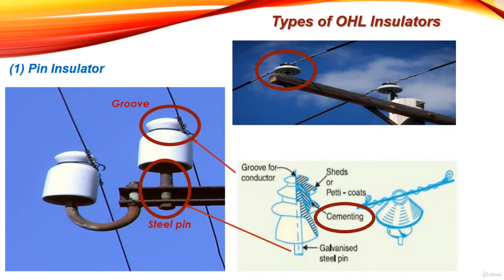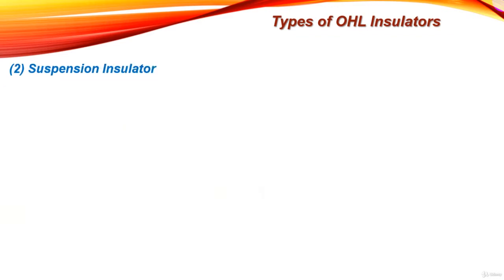Pin type insulators are used for transmission and distribution of electric power at voltages up to 33 kilovolts. Beyond an operating voltage of 33 kilovolts, pin type insulators become too bulky and hence uneconomical. So when the voltage increases above 33 kilovolts, the solution is to use a suspension insulator.